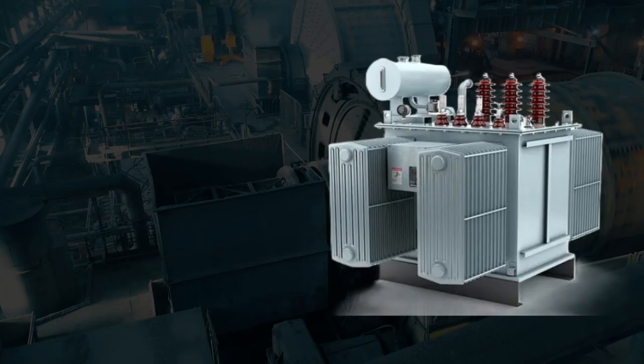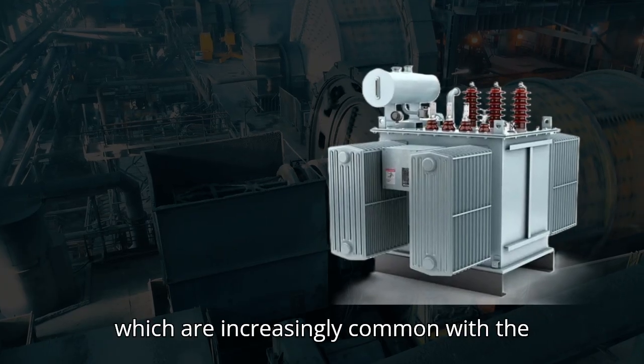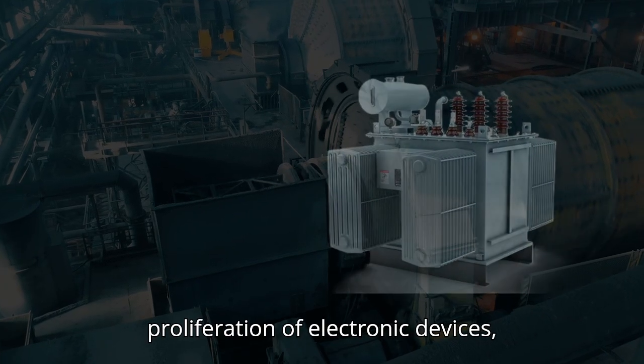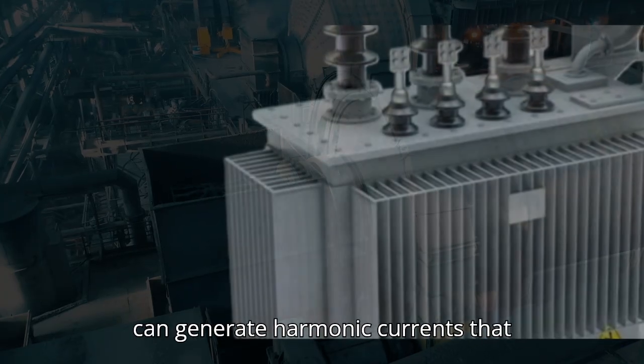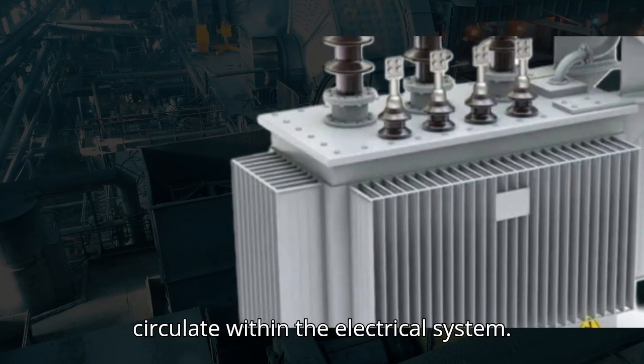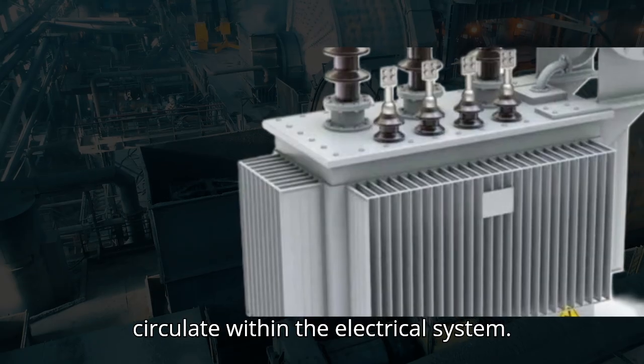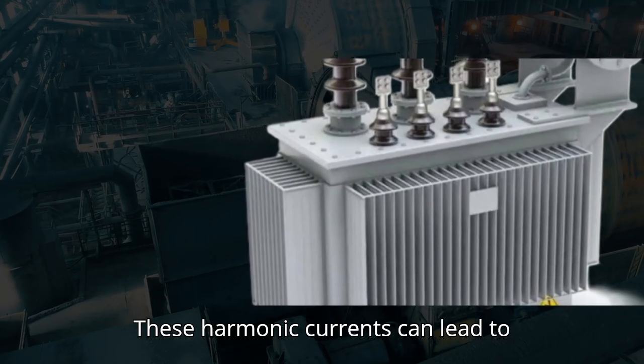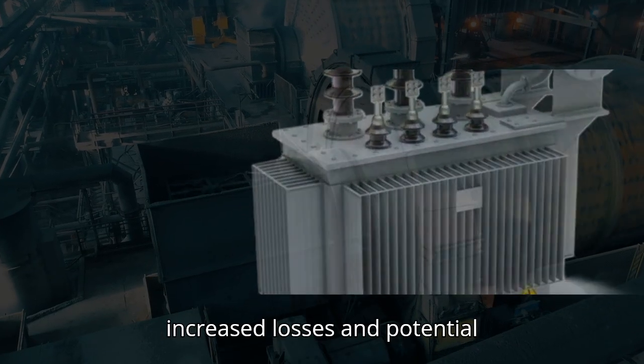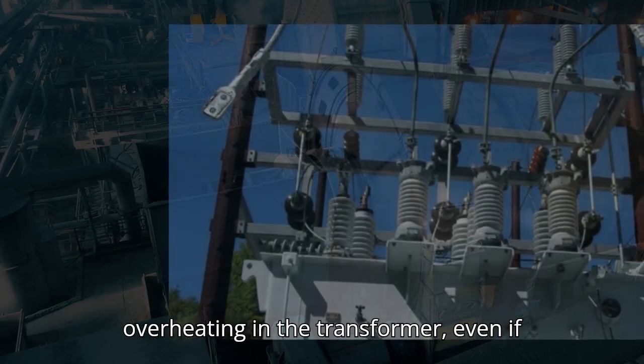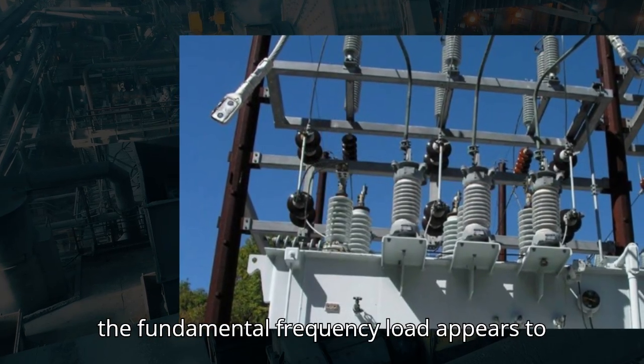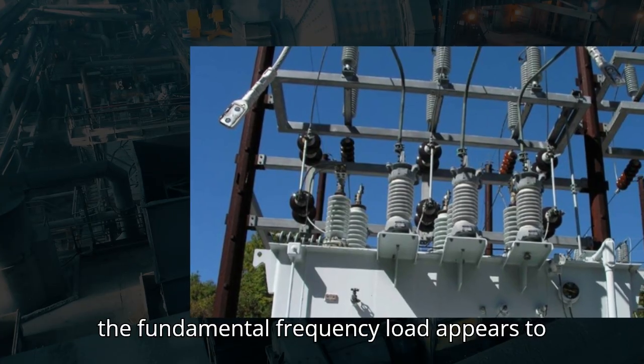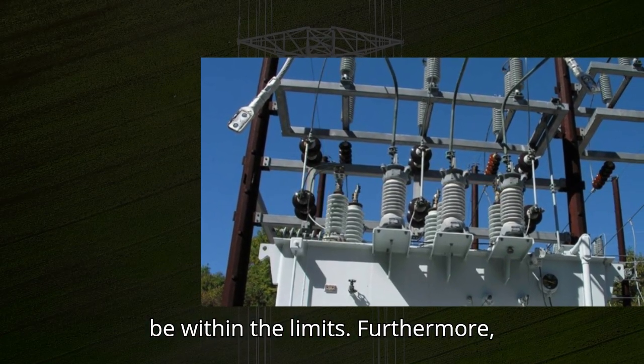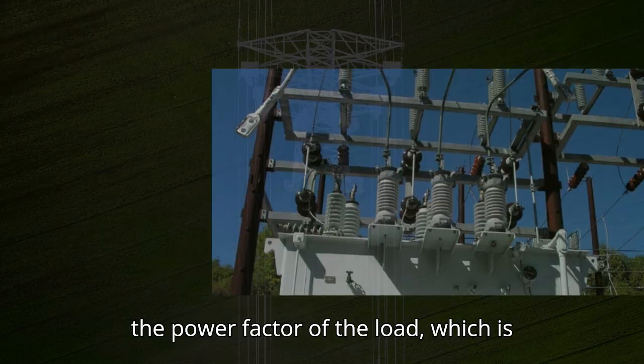rating. Similarly, nonlinear loads, which are increasingly common with the proliferation of electronic devices, can generate harmonic currents that circulate within the electrical system. These harmonic currents can lead to increased losses and potential overheating in the transformer, even if the fundamental frequency load appears to be within the limits.